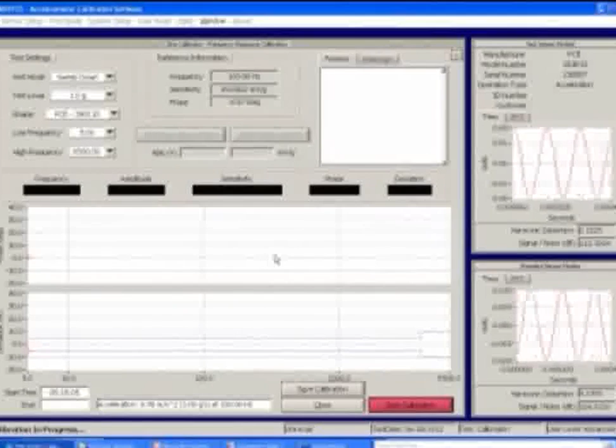Once we start the calibration, the system goes through its safety checks and then starts the calibration process. Even if we have a sensor that's out of spec, it's a very easy interface to see where the failures are—it pops up bright red and lists exactly what the out-of-tolerance condition was.